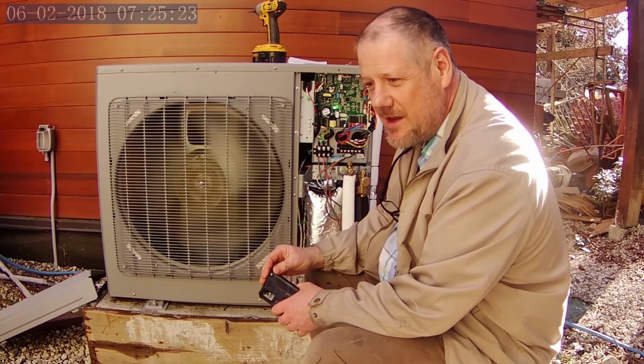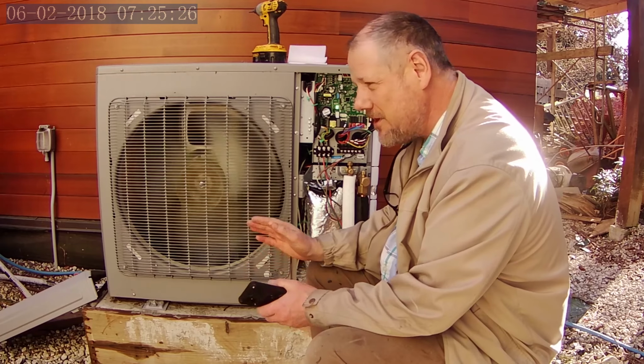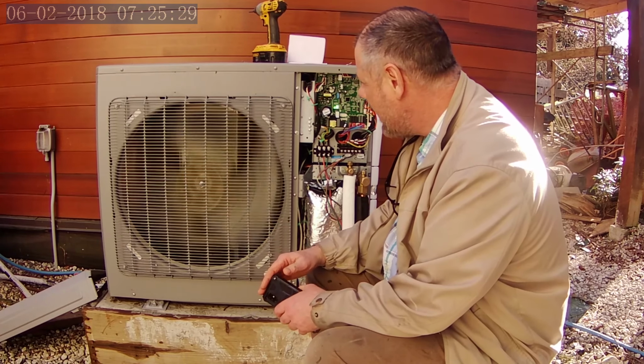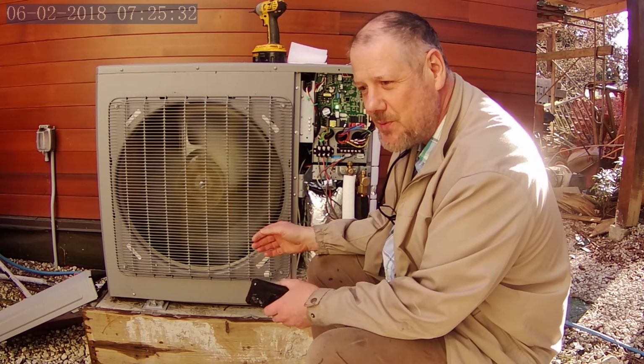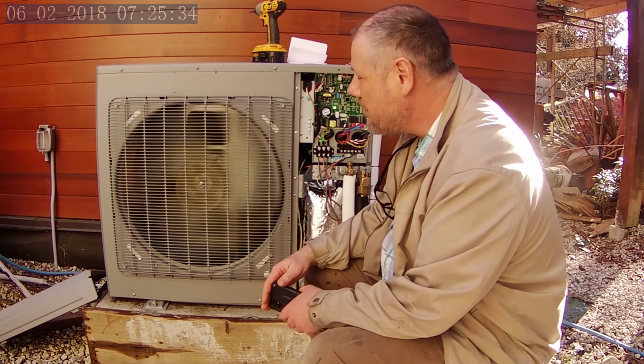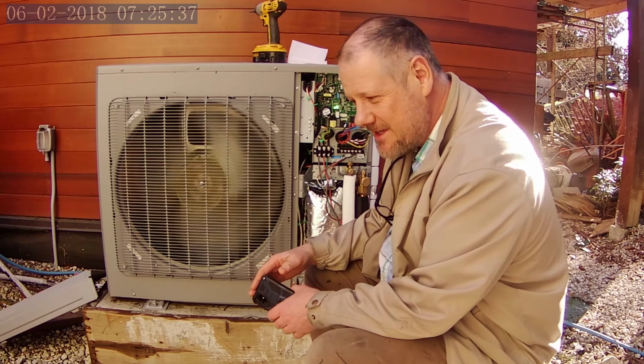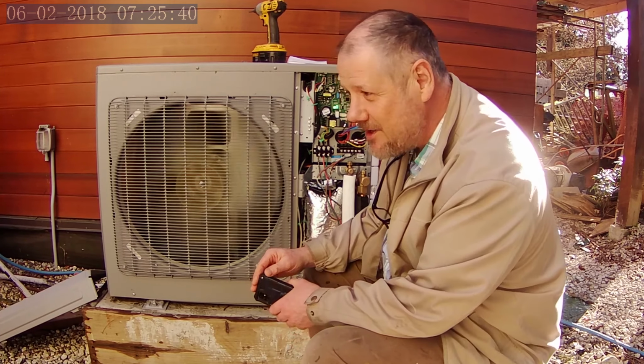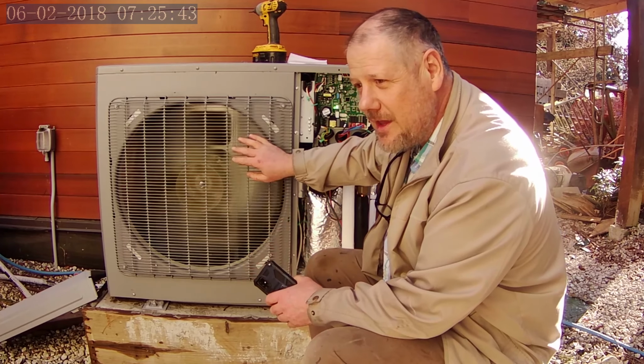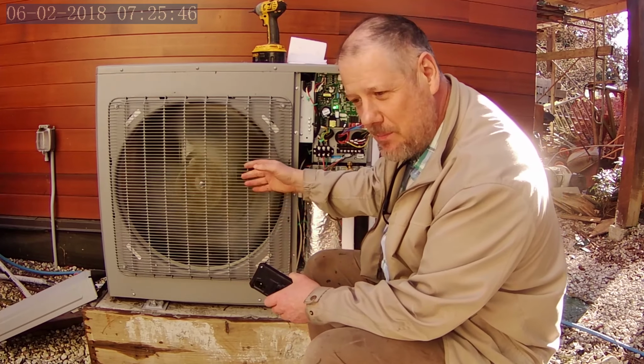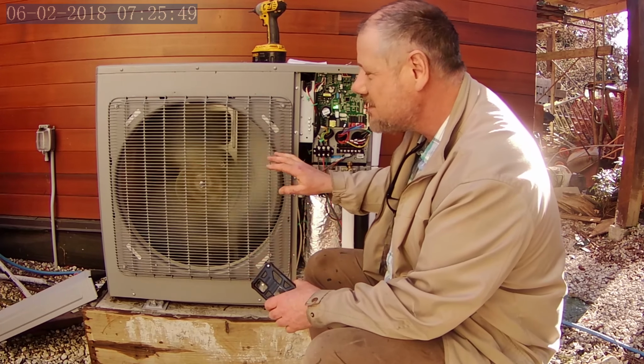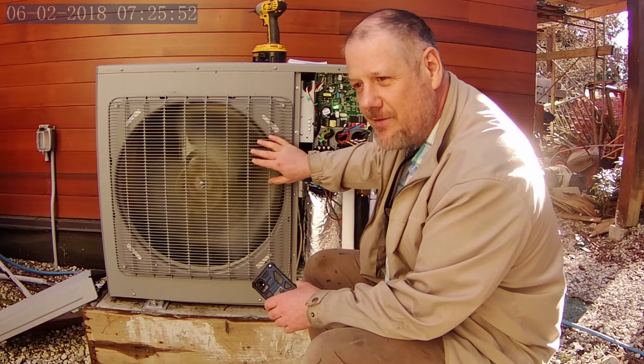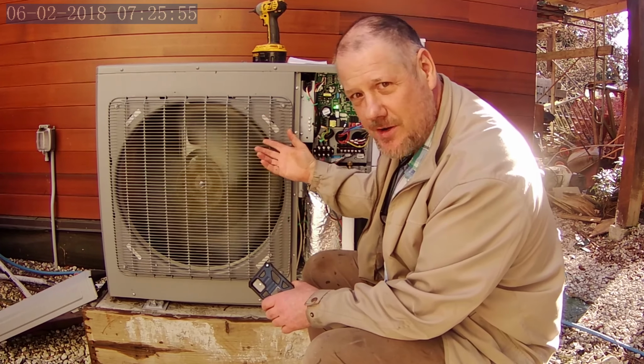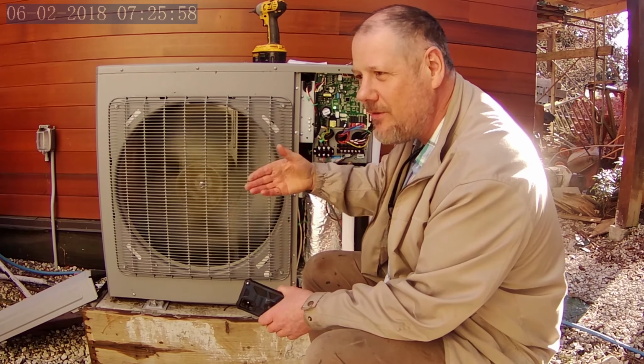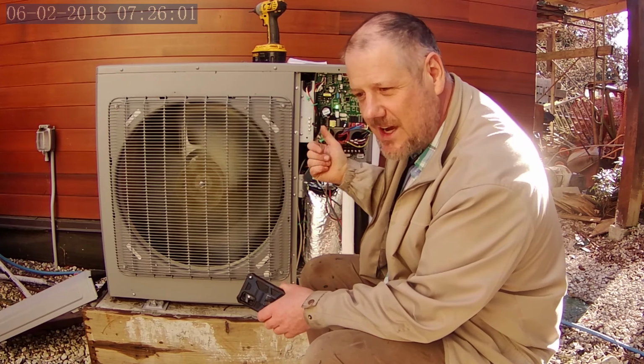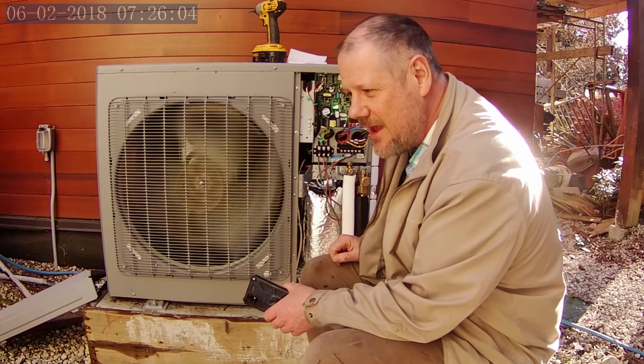So we've been testing it overnight. It's been running well. The refrigerant charge seems to be fine. We're now trying to, because this is a prototype match between the GREE inverter heat pump and the ThermAtlantic DX2W-EX1 indoor module, and he hasn't worked with these before, he being Benoit at ThermAtlantic, we don't necessarily know the inner workings of the GREE and how it's going to respond to the indoor module. So we're going through a few different tests on flow rates inside on the buffer tank circuit.